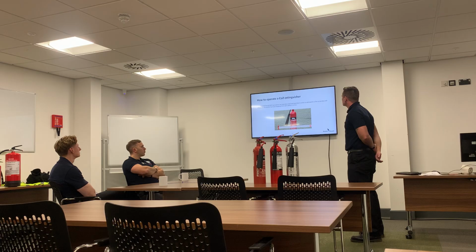Carbon dioxide or CO2 extinguishers are signal red with a black panel. They are suitable for use on Class B fires and those involving electrical equipment. To use a CO2 extinguisher, position the discharge horn, as it will be too cold to do so when the extinguisher is being used. Pull the safety tag to break the seal.